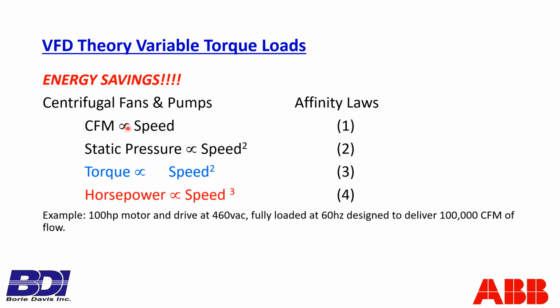The cubic feet per minute of flow is directly proportional to speed. They're a linear relationship. The static pressure or torque in the system is a square function. That is to say, again, at 100% speed, I'll need the full 100 horsepower out of the motor, and the torque required will be 100% squared. And 100% is 1, 1 squared is 1, so I'll need 100% torque at 100% speed. But at 50% speed, 30 hertz, delivering 50,000 CFM of flow, half flow, at 50% speed, the torque and static pressure required will be 0.5 times 0.5 equals 0.25, 25%.